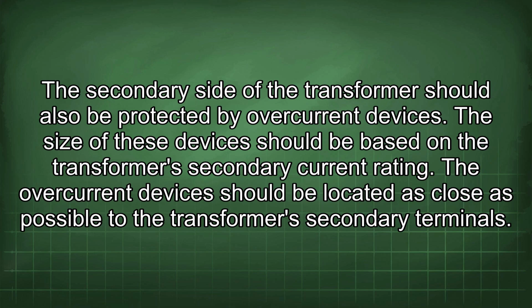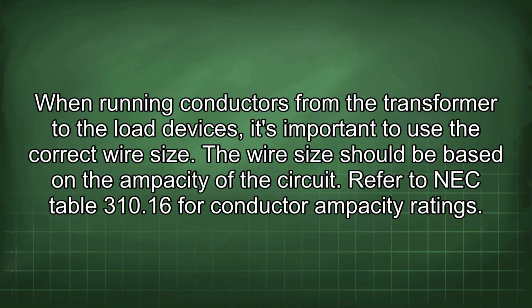The overcurrent devices should be located as close as possible to the transformer's secondary terminals. When running conductors from the transformer to the load devices, it's important to use the correct wire size. The wire size should be based on the ampacity of the circuit. Refer to NEC Table 310.16 for conductor ampacity ratings.